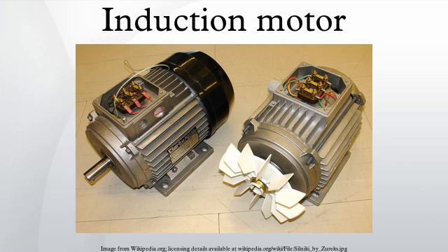Steinmetz equivalent circuit. Many useful motor relationships between time, current, voltage, speed, power factor and torque can be obtained from analysis of the Steinmetz equivalent circuit, a mathematical model used to describe how an induction motor's electrical input is transformed into useful mechanical energy output. The equivalent circuit is a single-phase representation of a multiphase induction motor that is valid in steady-state balanced load conditions. The Steinmetz equivalent circuit is expressed simply in terms of the following components: stator resistance and leakage reactance, rotor resistance, leakage reactance, and slip. Magnetizing reactance.